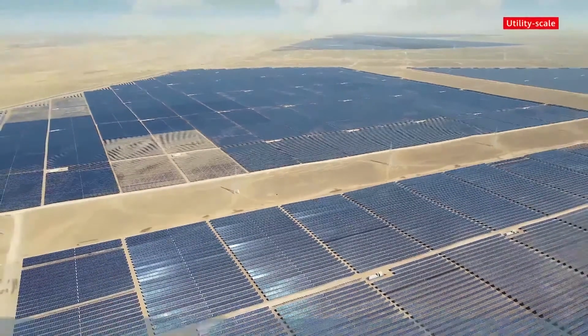Grid forming is a technology that gives PV voltage source attributes and aligns grid-tie features with synchronous generators. We need to completely overhaul the control. We need to proactively control the frequency and voltage using the 1500 double string and grid forming, and we have achieved a good mechanism to control the voltage source. Recently, together with Qinghai Grid, we did a research, and our research shows that the PV generating mode has increased the efficiency of renewable energy access. It has boosted the efficiency by 13%.